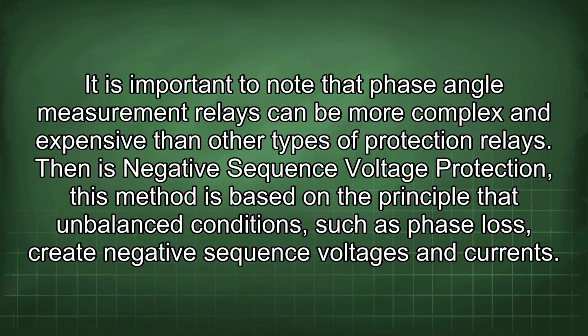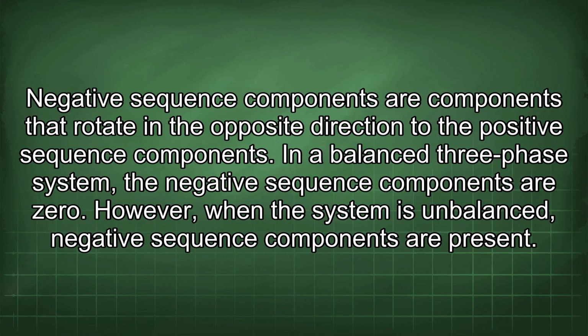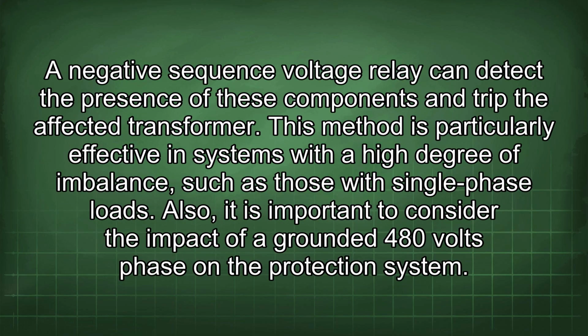Then is negative sequence voltage protection. This method is based on the principle that unbalanced conditions, such as phase loss, create negative sequence voltages and currents. Negative sequence components are components that rotate in the opposite direction to the positive sequence components. In a balanced three-phase system, the negative sequence components are zero. However, when the system is unbalanced, negative sequence components are present. A negative sequence voltage relay can detect the presence of these components and trip the affected transformer. This method is particularly effective in systems with a high degree of imbalance, such as those with single-phase loads.